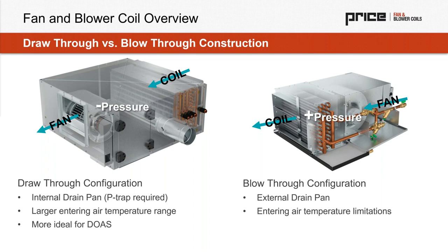In this case, the positive pressure is going to push that fluid out through those drain slots and into an exposed neutral pressure drain pan. We're going to be able to manage condensate much more easily at that point. It would actually drain with gravity, although we traditionally see these still installed with some kind of condensate pump in both cases, just because it's good practice. And the worst thing we can have is leaks or fluid at large within a building. We need to make sure we manage that effectively.